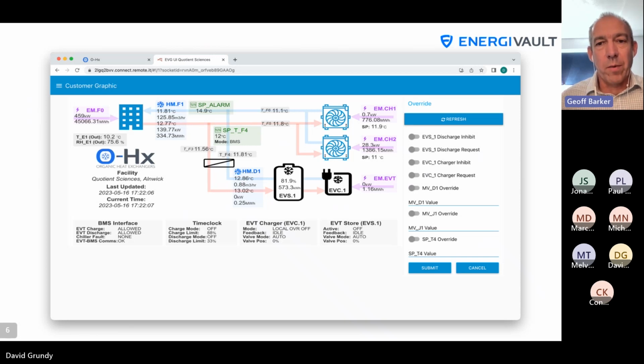Similarly, you can do that by the BMS setting the temperature at which it wants each of those chiller elements to come on. So fundamentally, you're connecting the EnergiVault to the existing BMS, and the BMS remains in control of the overall chiller plant, but it knows what the available capacity in EnergiVault is, and it can determine when and how it deploys it. Now, throughout the year, there are different priorities.